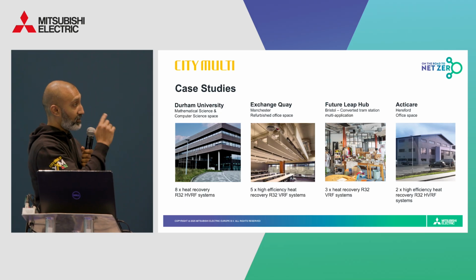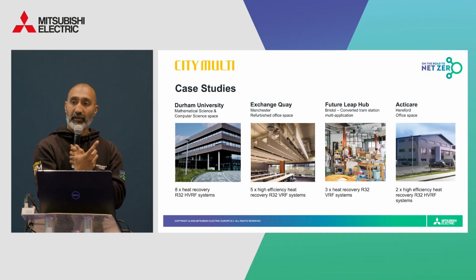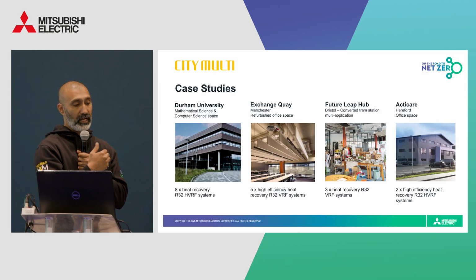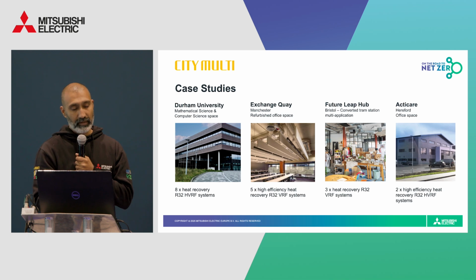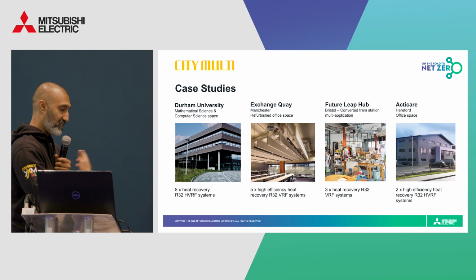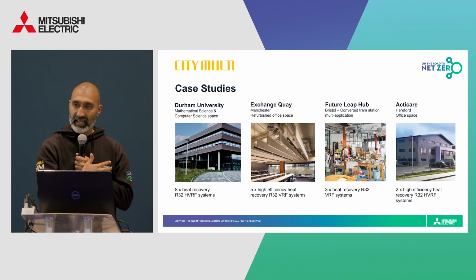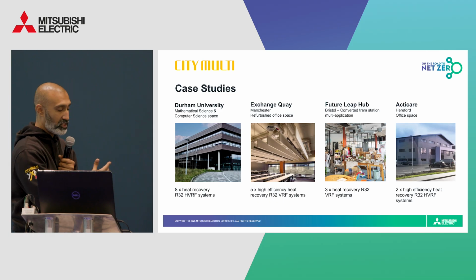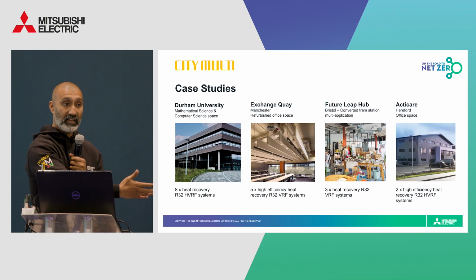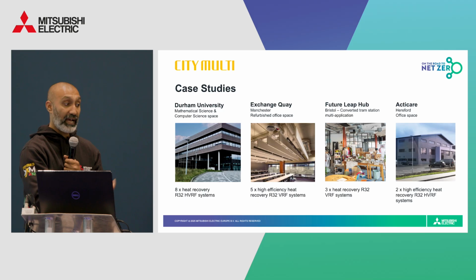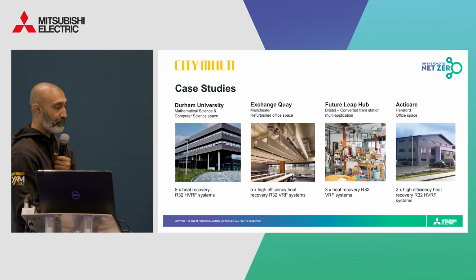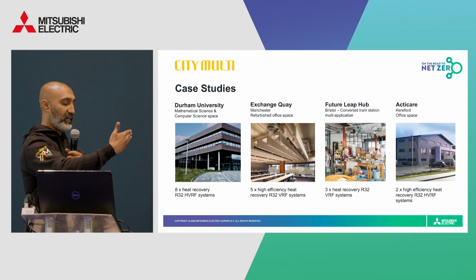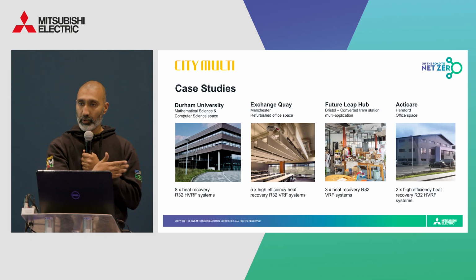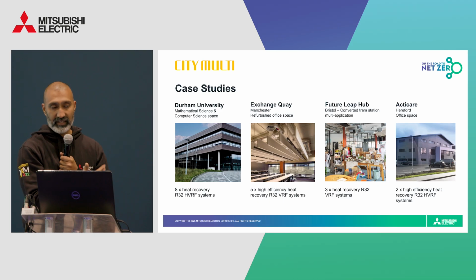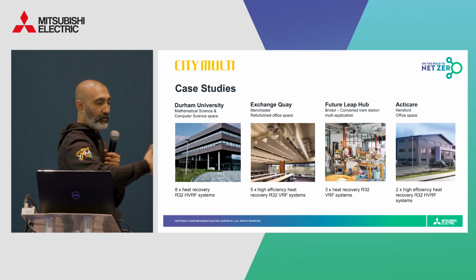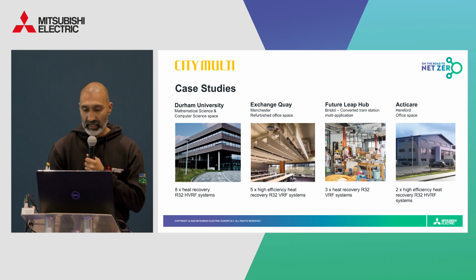And if we take Durham University, for an example, they decided to go down the route of R32 HVRF because they wanted to future-proof their building and also try and reduce the embodied carbon. So with HVRF, well, they still get that plug-and-play flexibility that you get with any traditional VRF solutions. And then, as mentioned, the refrigerant's just between the outdoor unit and the HBC box, so significantly lower overall system volume, and they chose to go down the R32, so lower GWP. Plus, the future-proofing element. Because the connection from the HBC box to the indoor unit is just traditional water piping, if a new refrigerant comes along and they need to do an upgrade or any change, that second half of the system from the HBC box to the indoor unit can remain unchanged.